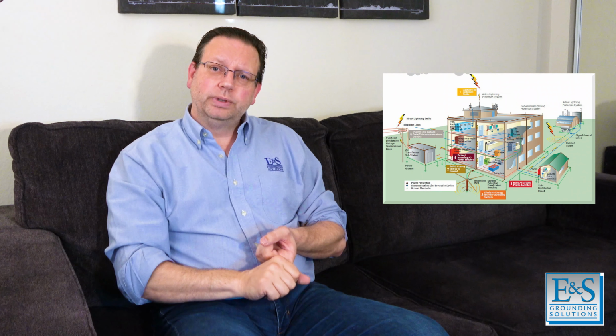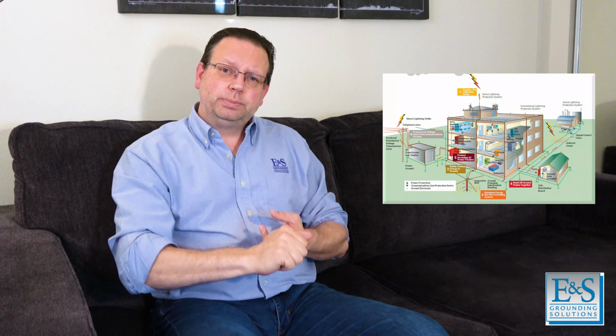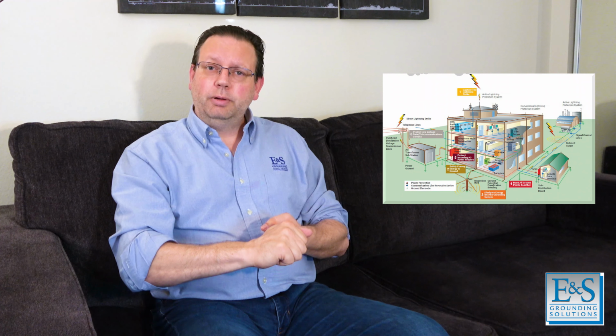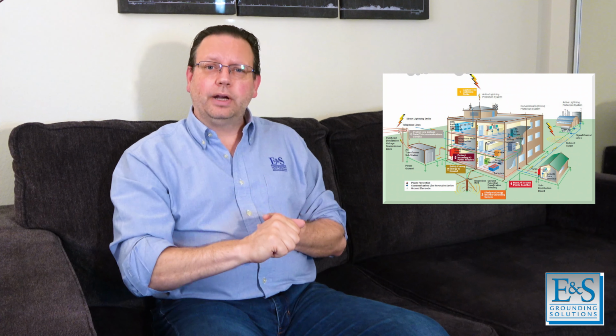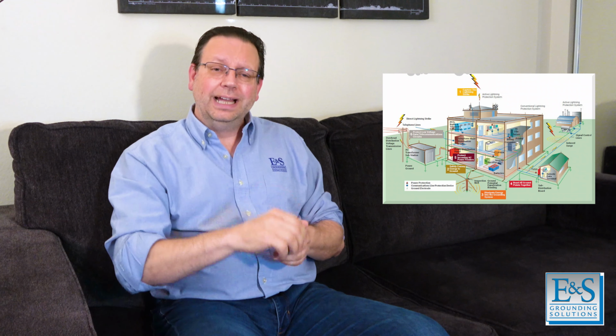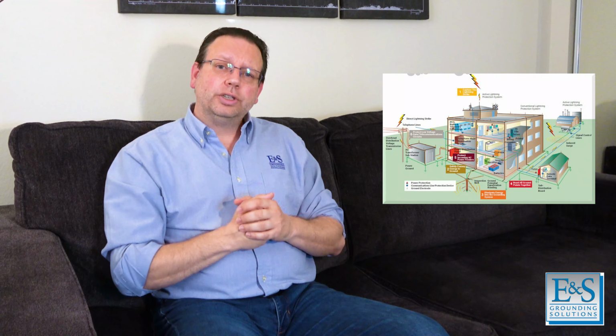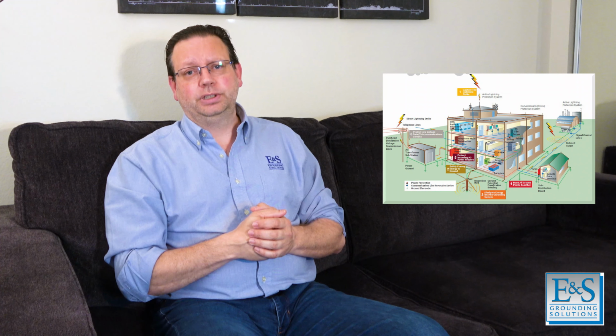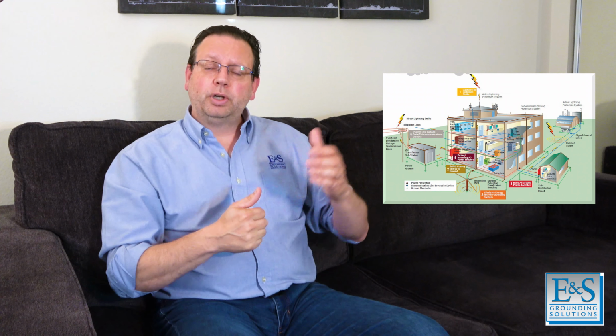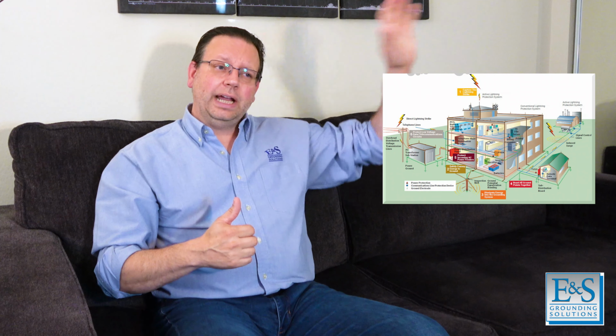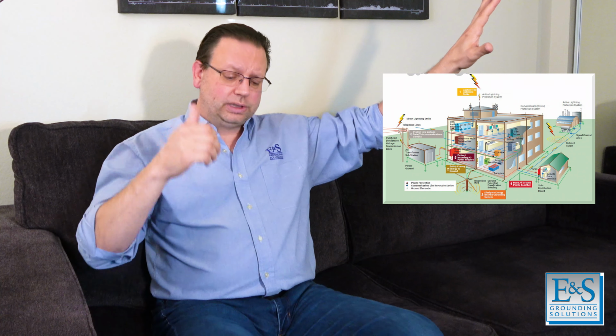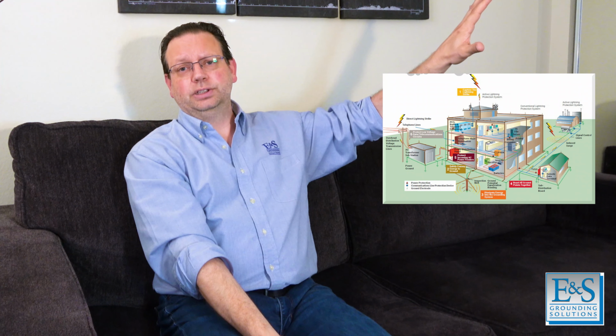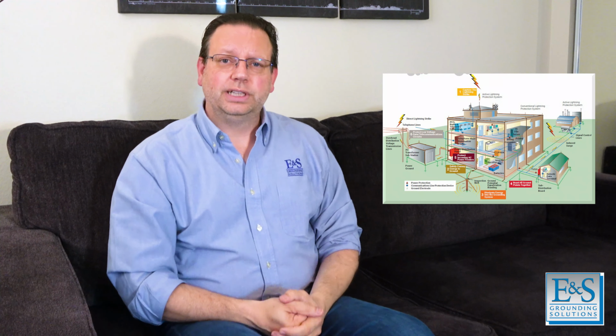You're going to have a much lower resistance to ground, a much better ability to handle and divide and conquer and get rid of that current efficiently and safely. And if you have people leaning or touching against the building, you're also inherently helping to provide a step and touch voltage safety network for personnel that might be leaning on the building during a lightning strike, because now their hand might be at 1,000 volts, but their feet will be energized as well. You'll have to go back to our step and touch voltages to gain that.